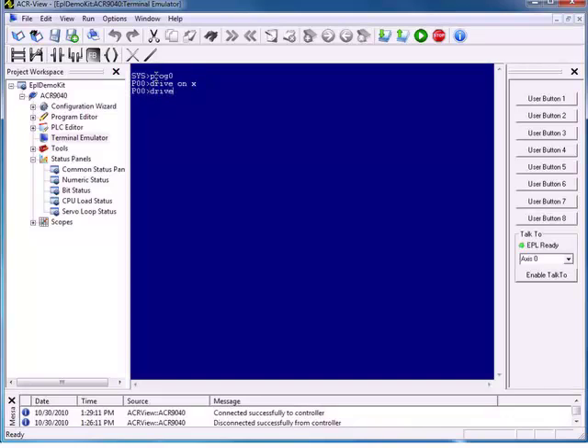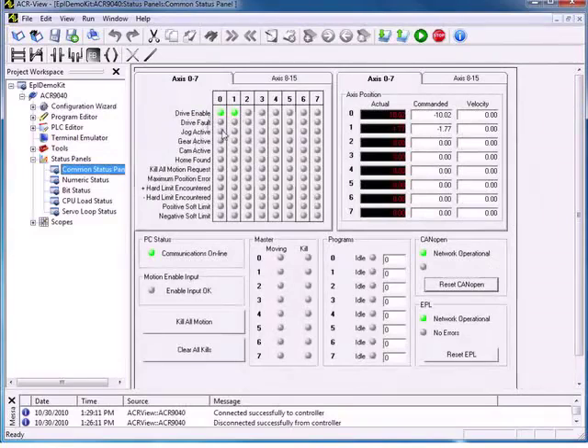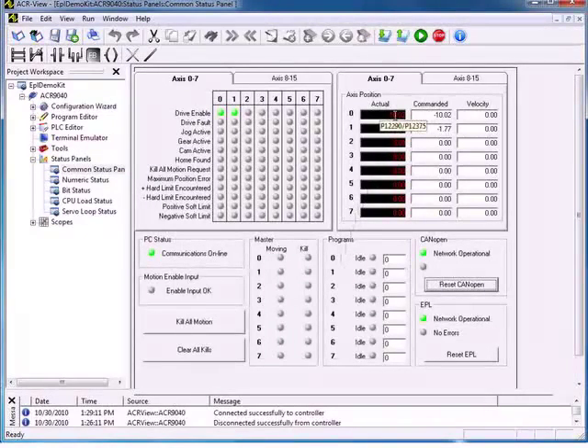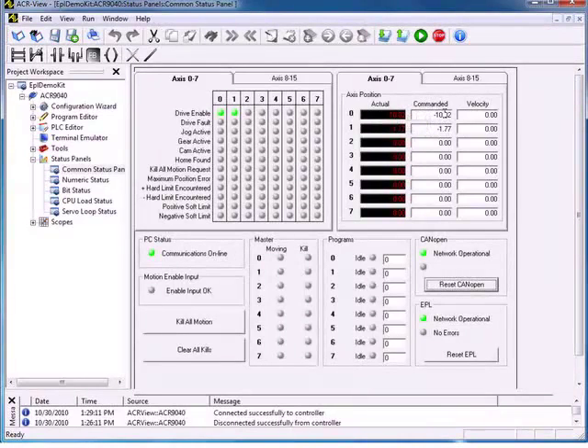We're going to return to the common status panel. You can see now that the drives are enabled, we have no faults, and everything looks good. We can see our actual and commanded position for the drives and we can see that they are not moving. One nice feature of the panel is if we hover over one of these objects, it will give us the parameter numbers. We can see that our parameter number is 12290, and the commanded is P12375.